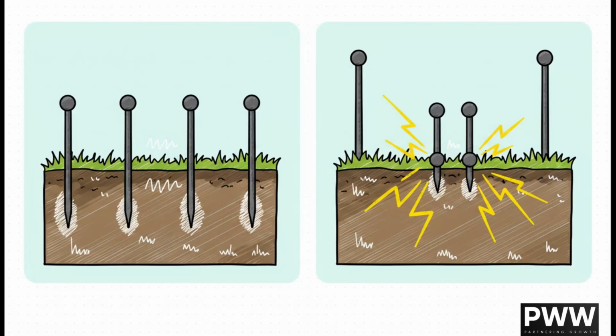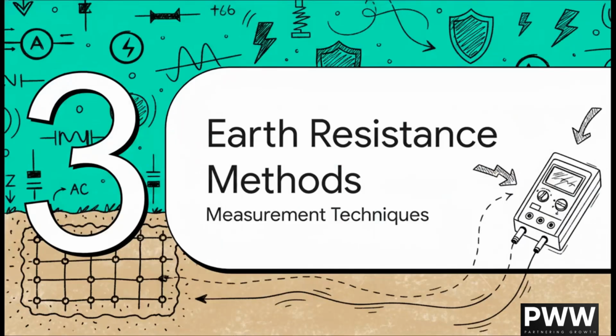But hey, what happens when you need to scan way deeper into the soil? Well, you increase the spacing. The catch is, with the Wenner arrangement, as spacing gets very large, the potential reading between those inner electrodes drops rapidly. Oftentimes, commercial instruments just struggle to pick up those tiny values. That is exactly where IEEE 81 suggests switching to the Schlumberger-Palmer arrangement. By keeping the inner potential probes closer to the outer current electrodes, you artificially boost the voltage signal, entirely overcoming the limitations of your meter over those massive distances. Pretty clever, right?